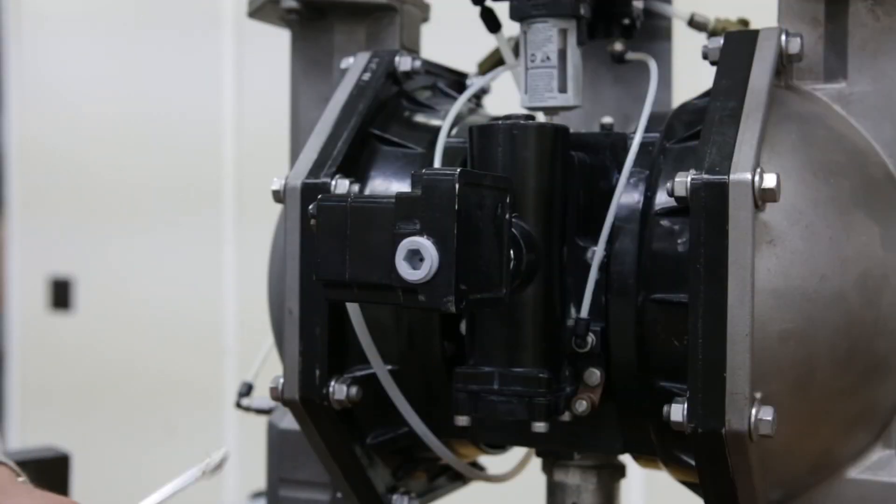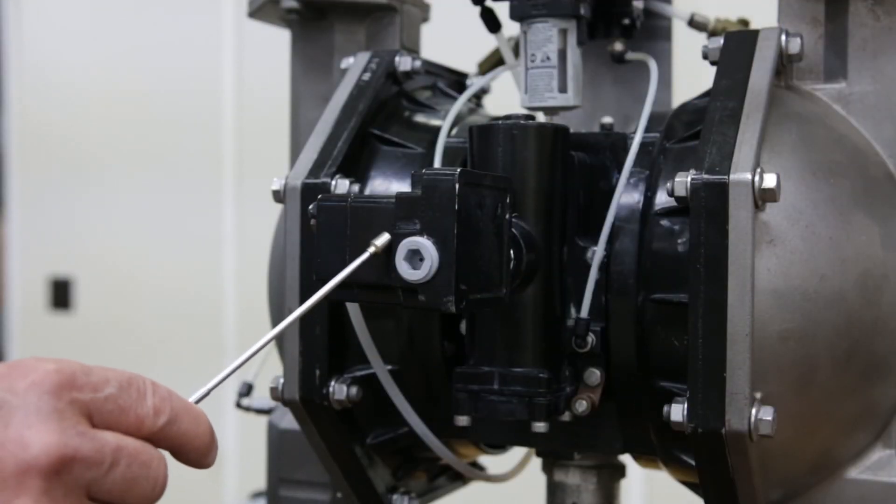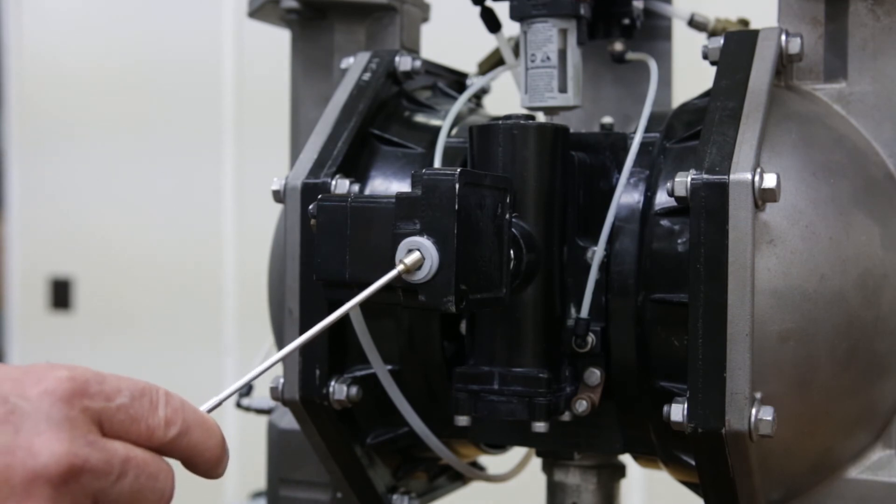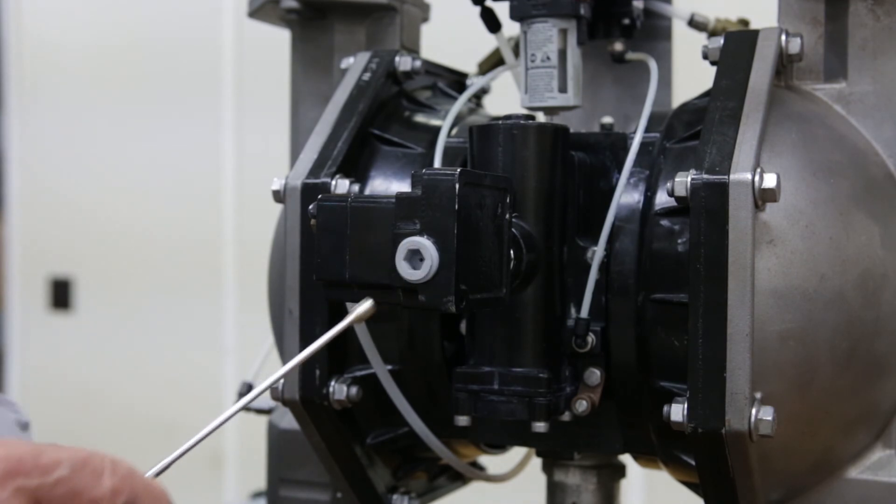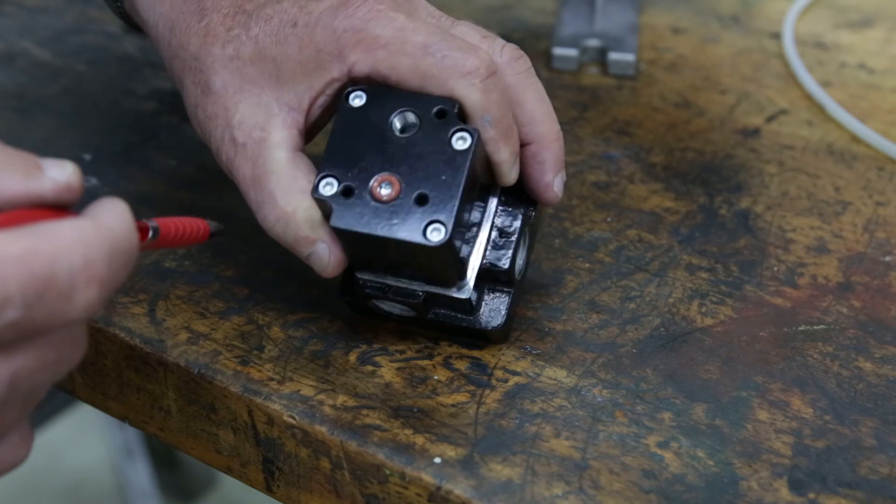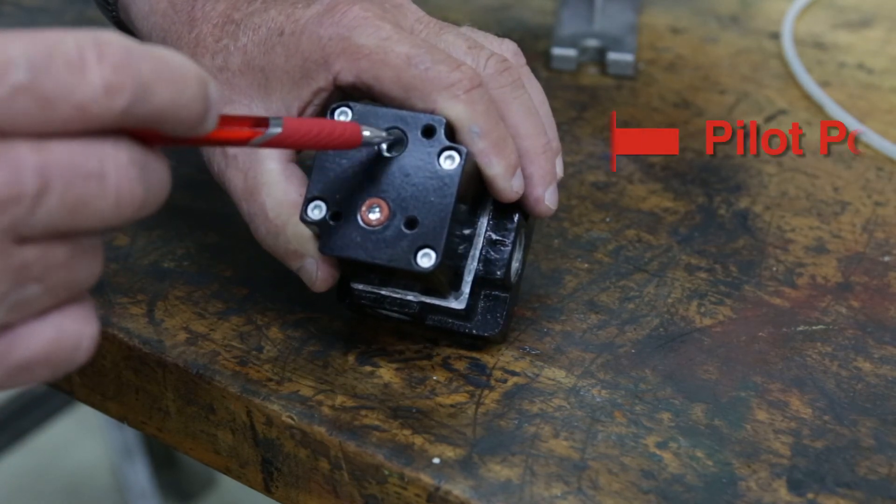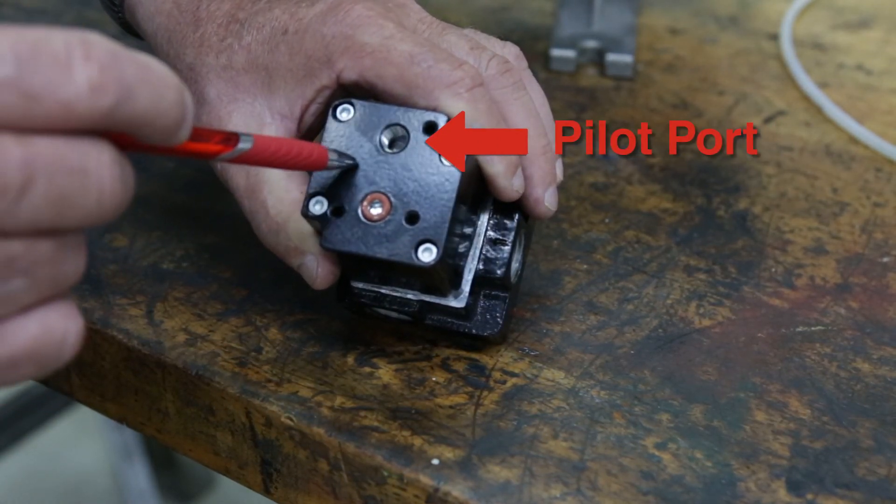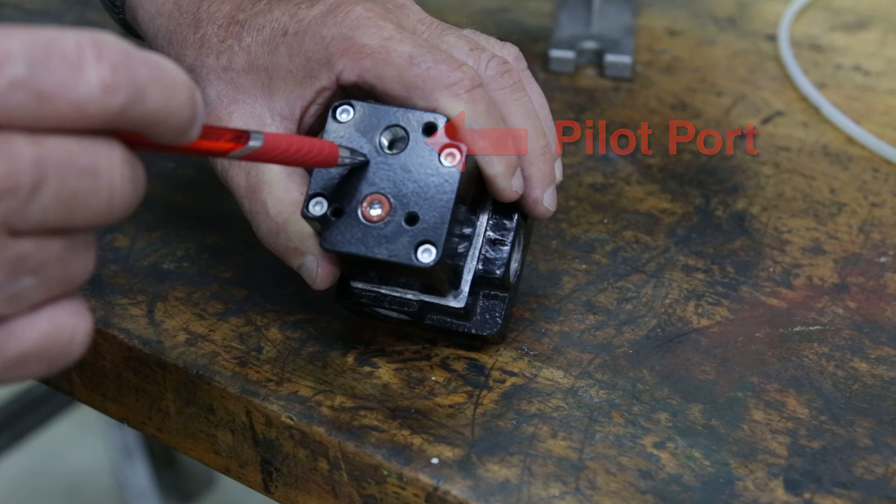There's a plastic plug with a small orifice drilled into it. The purpose of this plug is to make sure that debris does not filter back into the valve. On top of the valve, you'll see another port. This is the pilot port. This valve has a small accumulator built into it, so if you meter the air into the valve, there'll be a time delay before the valve turns on, after the air pressure is applied to the port. Normally, we have to reach approximately 30 psi before this valve will begin operating.